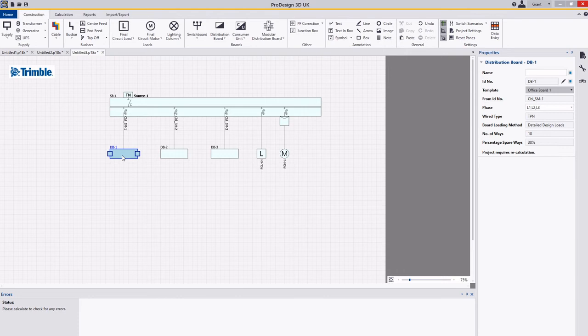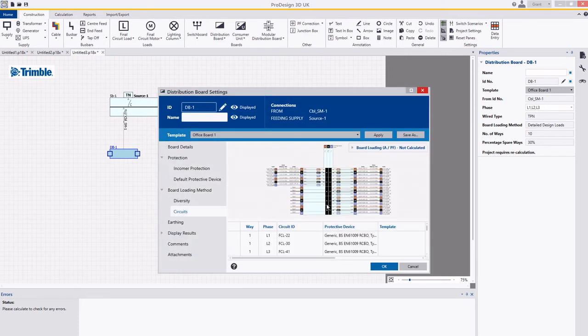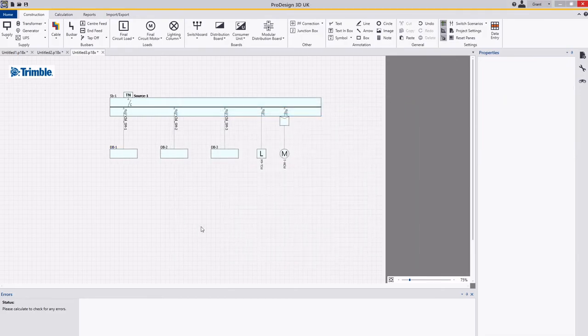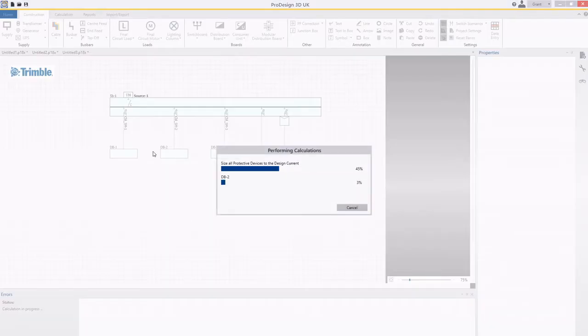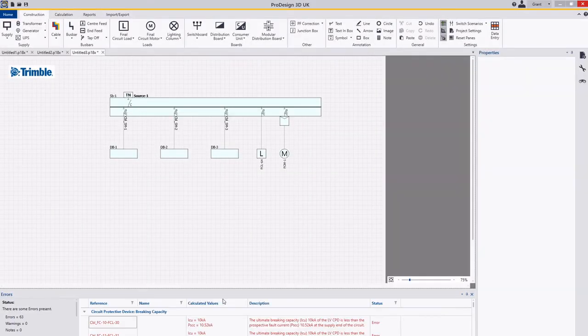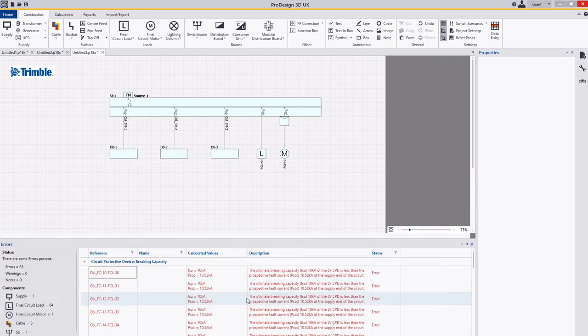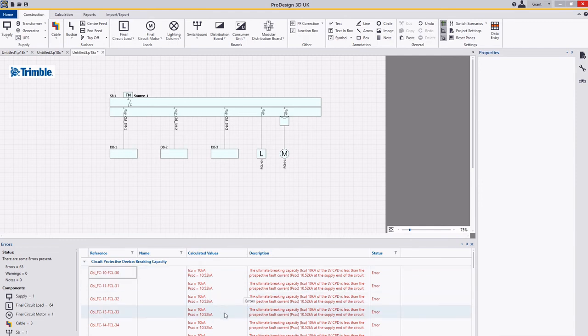So just going to go into here quickly, just show the different layouts. You can see here all the final loads are associated with it, and I can use F2 on my keyboard, run a quick calculation, and I can see where my issues lie. I've got fault issues in terms of breaking capacity for all the loads, and you can see there's 63 errors in this particular model.